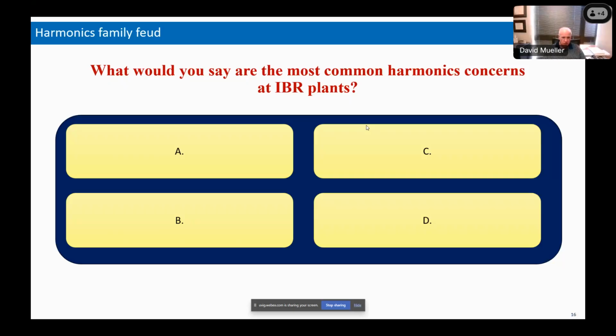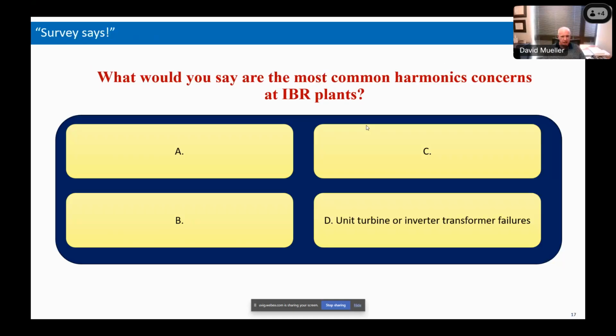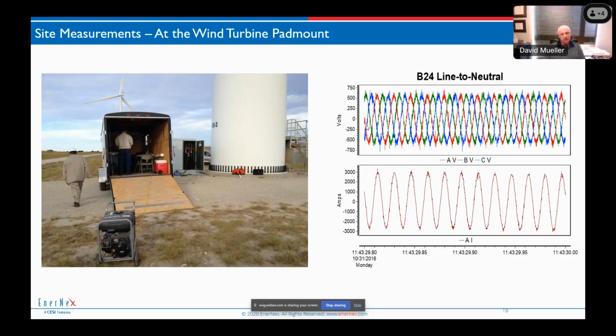So, okay, survey says: the first common harmonic concern at IBR plants is unit, turbine, or inverter transformer failures. Now, regarding transformer failure, I'm a guy who likes to say a transformer failure is a transformer problem. The transformer needs to be designed considering the fact that it's on a converter. It's going to see harmonics. It's going to see high frequency harmonics.